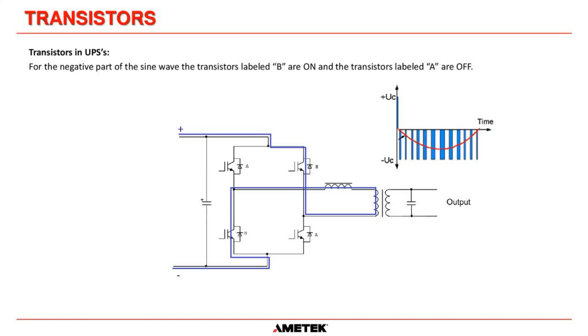We're still pulse width modulating on the bottom, and the mathematical average is still a sine wave. So that's how our inverter bridges work—we're just switching IGBT pair A on and then pair B on at 60 hertz. In the grand scheme of things that's what we're doing, but actually all these pulses mean we're switching at 8 kilohertz. Still the same principle.